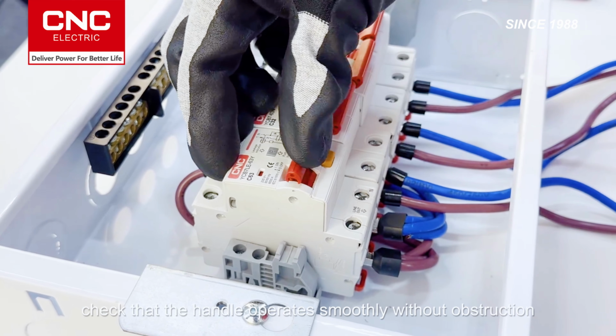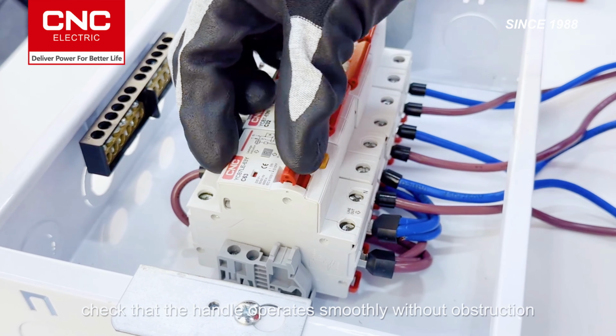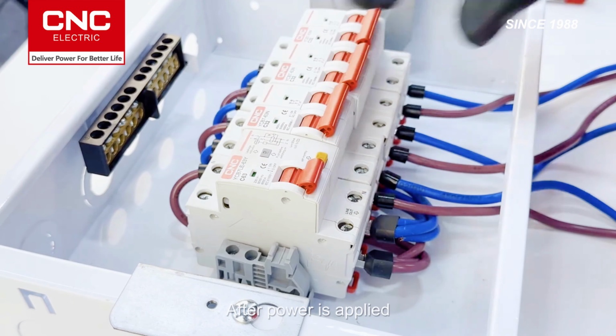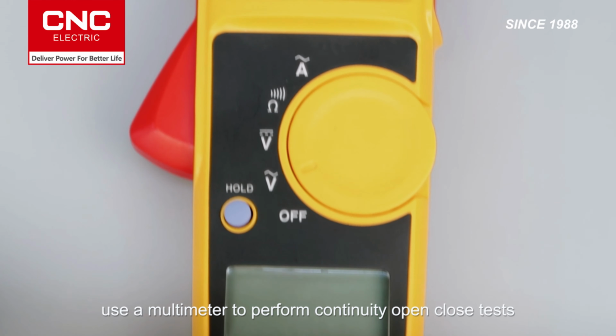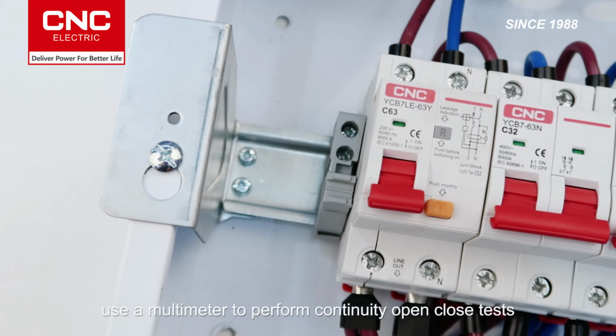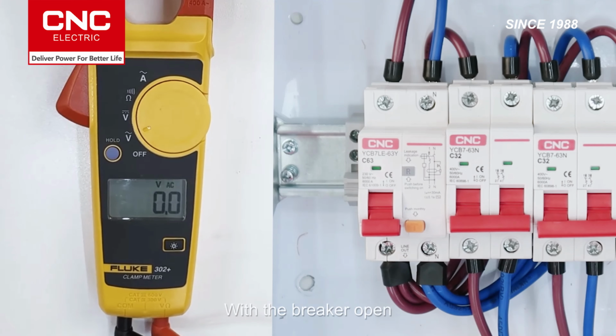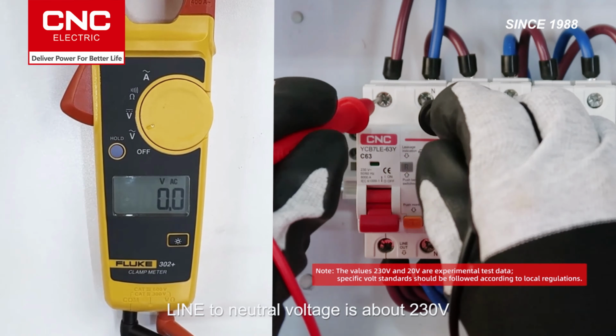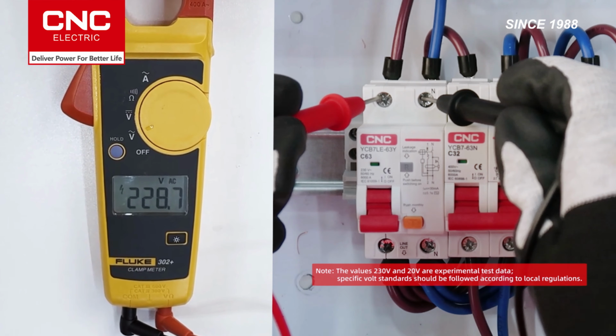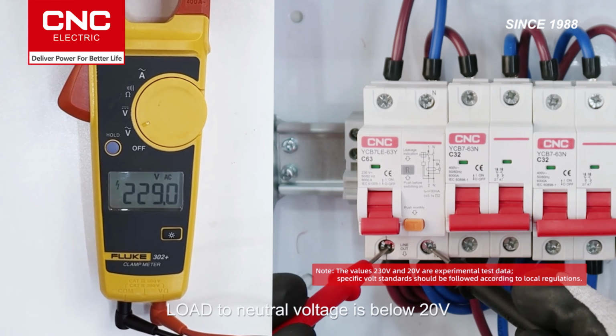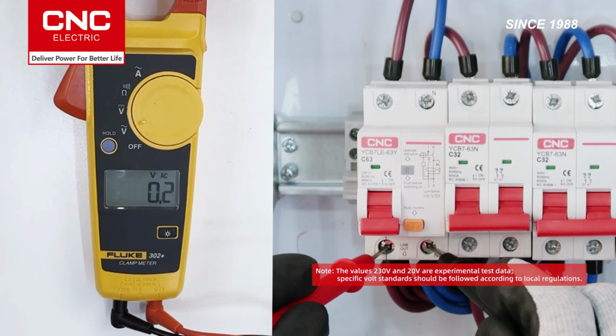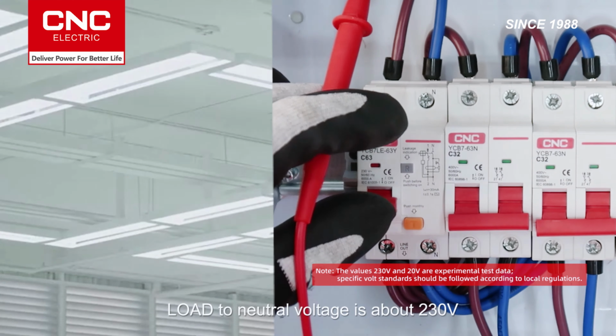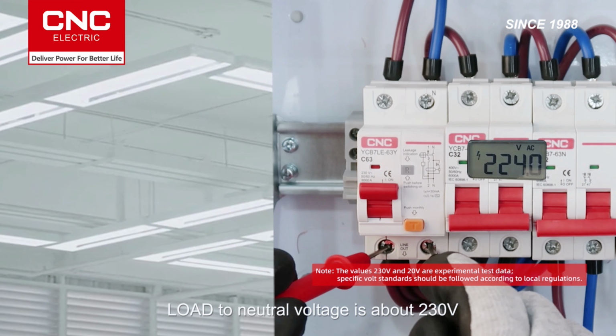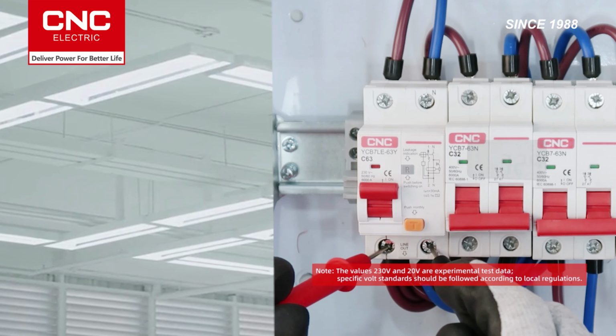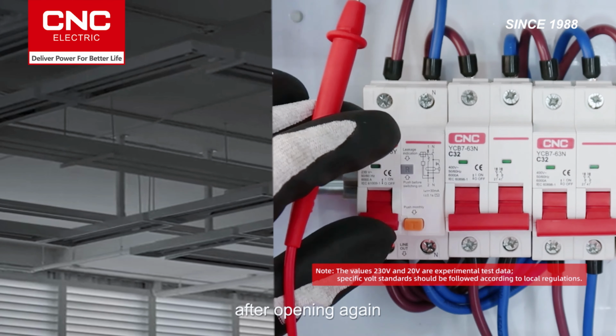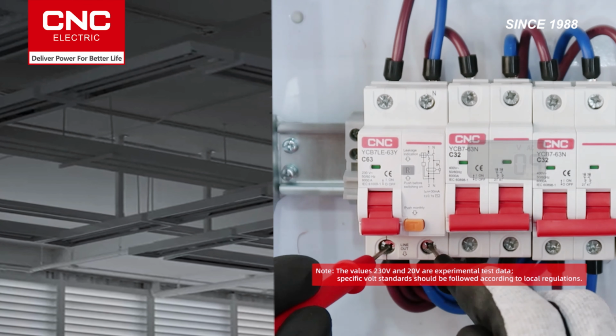Before energizing, check that the handle operates smoothly without obstruction. After power is applied, use a multimeter to perform continuity, open-close tests and confirm proper operation. With the breaker open, line to neutral voltage is about 230 V. Load to neutral voltage is below 20 V. When closed, load to neutral voltage is about 230 V. After opening again, it drops below 20 V.